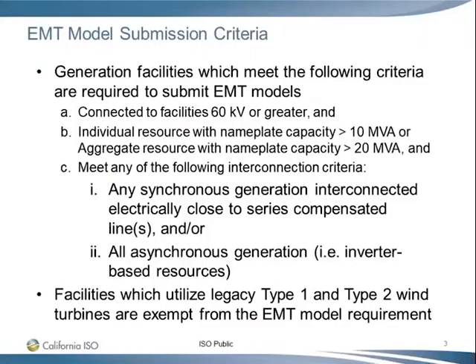So which resources must submit an EMT model? Really, I already mentioned it; if you can't memorize that instantaneously, you can see it here. If the resource is connecting to a facility at 60 kV or above, and the individual resource is greater than 10 MVA, or the aggregate resource is greater than 20 MVA, then it might be subject to EMT model. An additional requirement: if it is a synchronous generator close to a series compensated line, then it must submit an EMT model. Then all asynchronous generators must submit an EMT model, with the exception of type 1 and type 2 wind turbines. Type 1 and type 2, those are very old legacy wind farms. We don't require an EMT model for them.